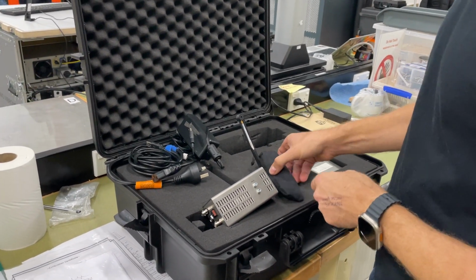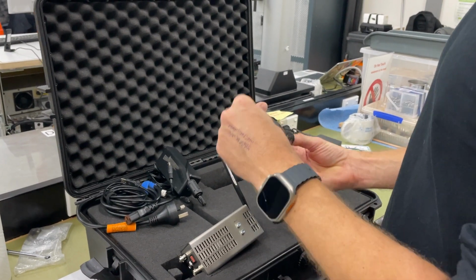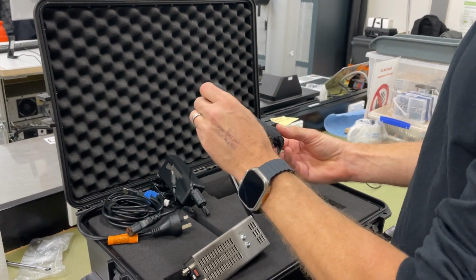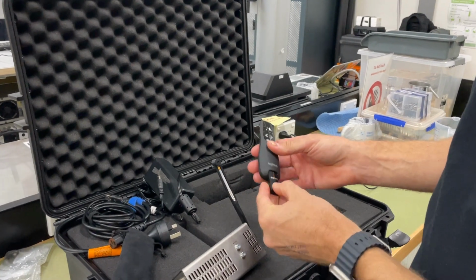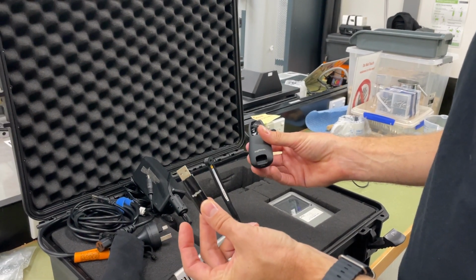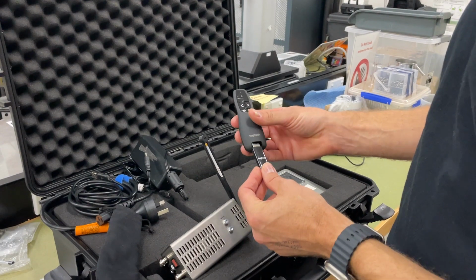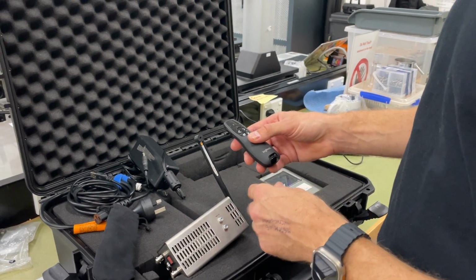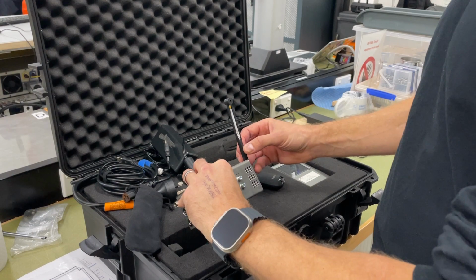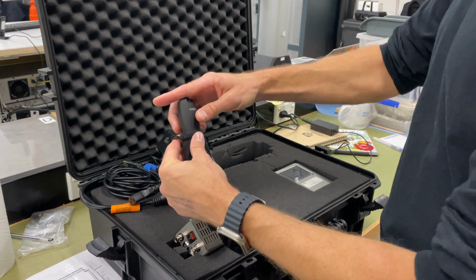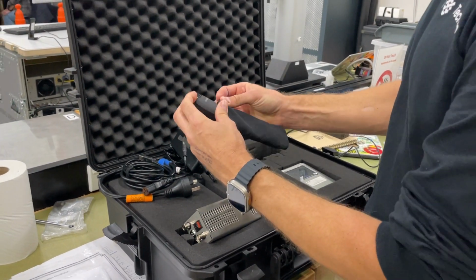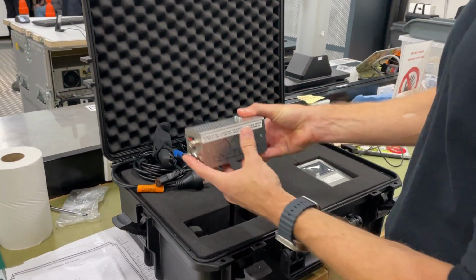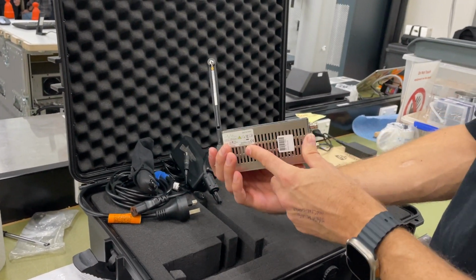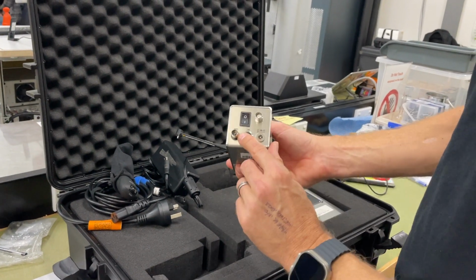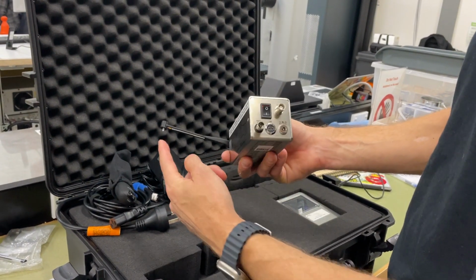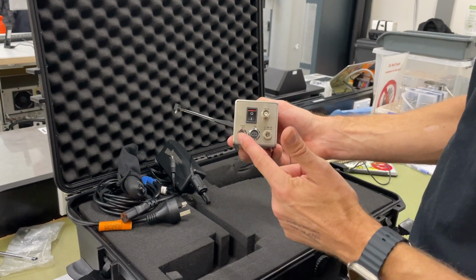So this one lives in here, and then there's also a laser pointer, which you might reasonably wonder why the laser pointer is included as well. This can be connected to the acquisition system PC, and then we can use the left and right keys in fact to drive the hammer backwards and forwards when we're setting the 0 position, but I'll describe that in more detail in the subsequent video. The hammer itself is in a very nice stainless steel casing now since we had it upgraded. Here is our signal out, which is for the force transducer. This needs to go into our acquisition system.